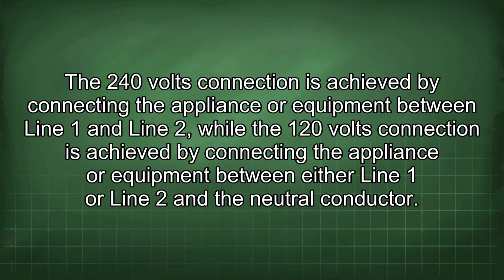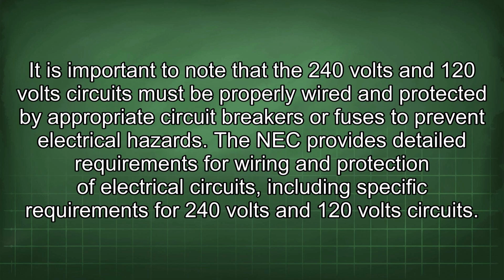The 240 volts connection is achieved by connecting the appliance or equipment between line 1 and line 2, while the 120 volts connection is achieved by connecting the appliance or equipment between either line 1 or line 2 and the neutral conductor. It is important to note that the 240 volts and 120 volt circuits must be properly wired and protected by appropriate circuit breakers or fuses to prevent electrical hazards.